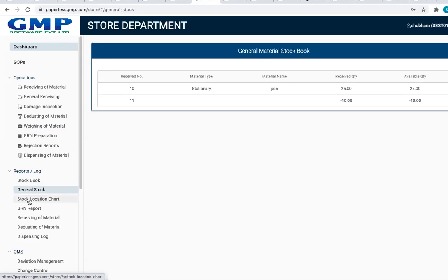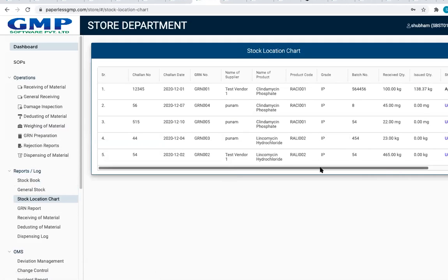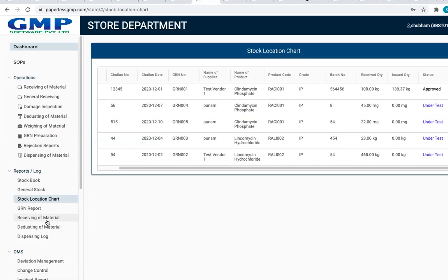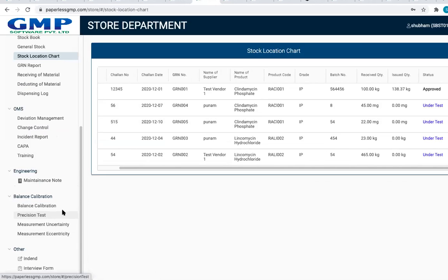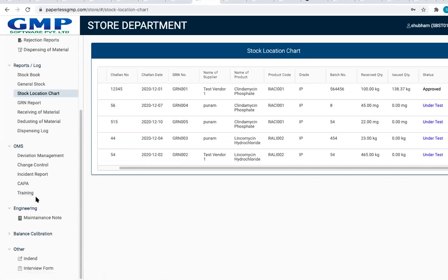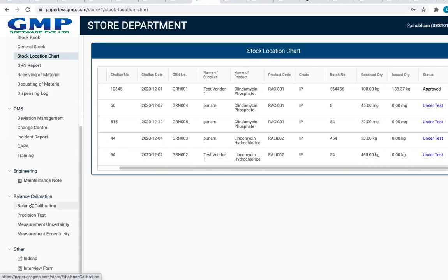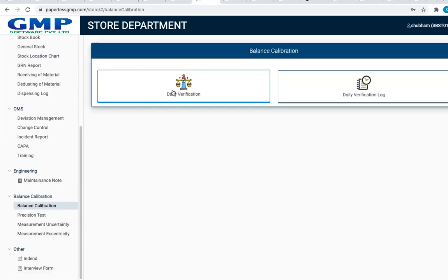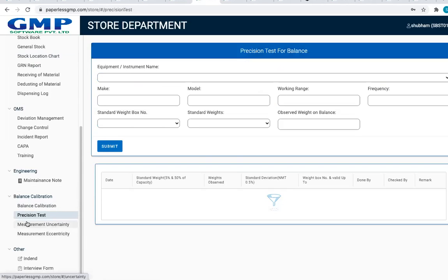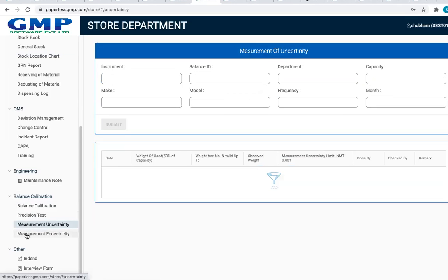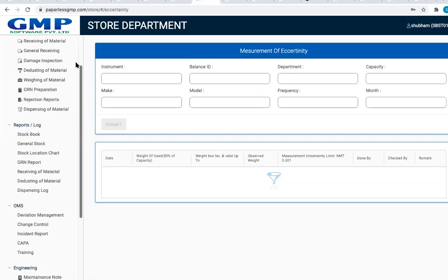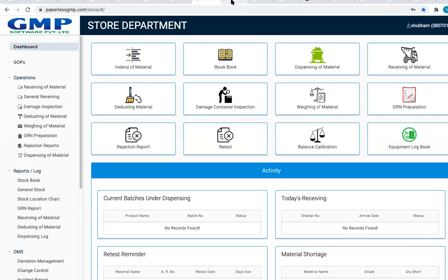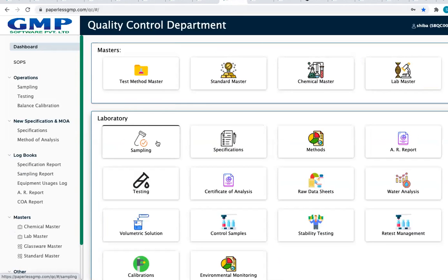This location chart, you can create your own location chart, and other quality system parts. Balance calibration has been given here. So daily verification of the balance, precision test, measurement uncertainty, measurement eccentricity. Then after preparation of GRN, the material will go to the QC department.